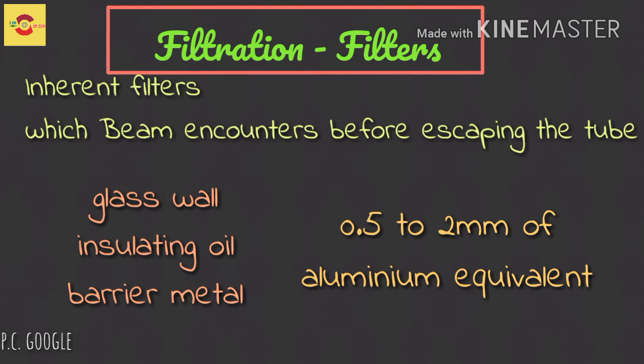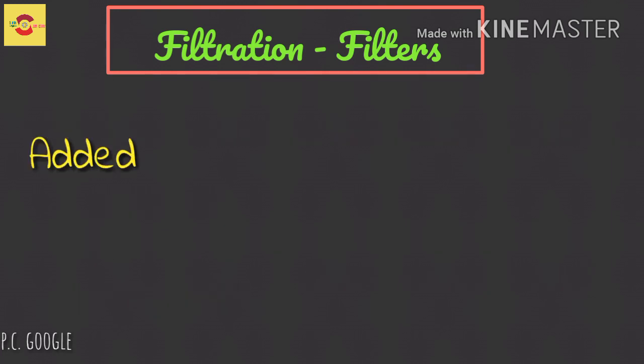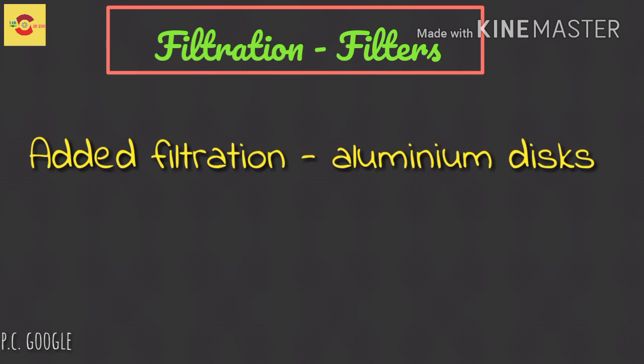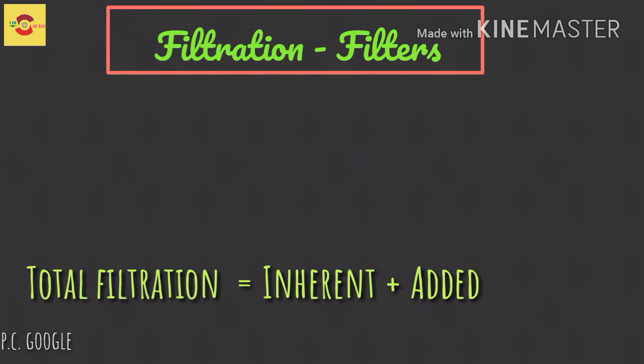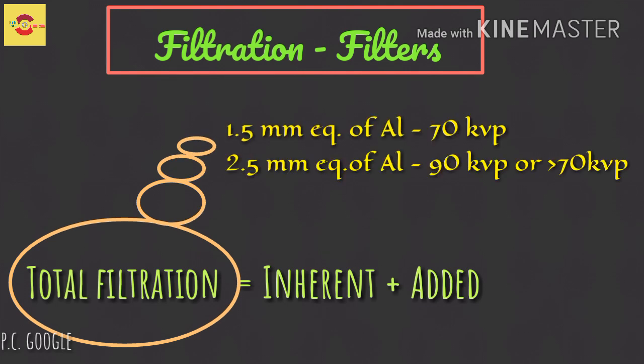Added filtration is supplied in the form of aluminum discs placed over the port in the head of the x-ray machine. Total filtration is the sum of inherent filtration and added filtration. Government regulations require total filtration to be equivalent to 1.5mm of aluminum for machines operating at 70 kVp and 2.5mm of aluminum equivalent for machines operating at higher voltages.